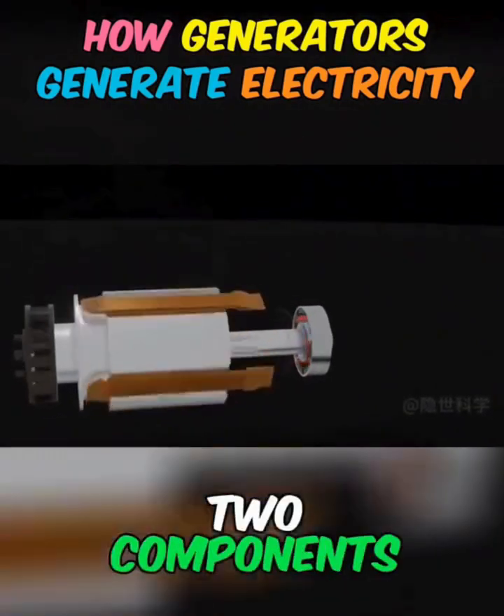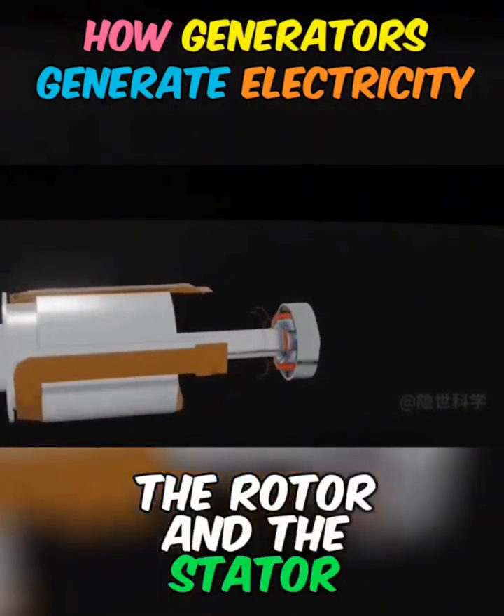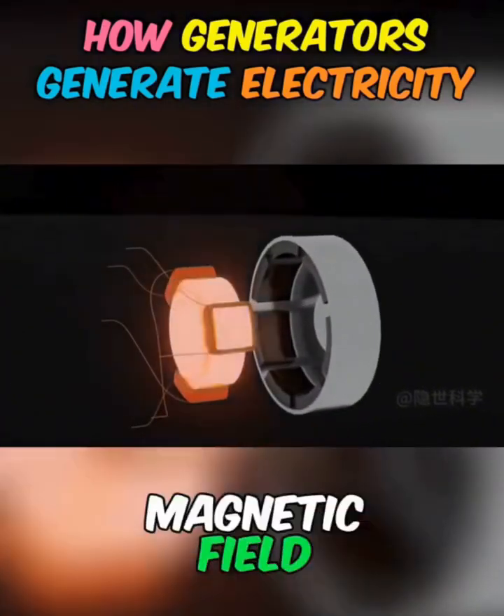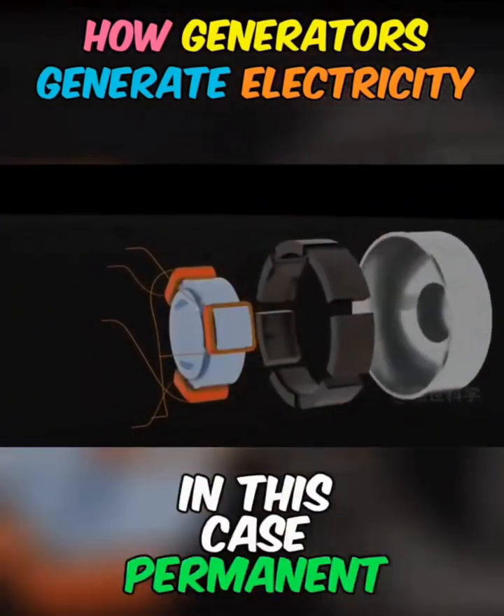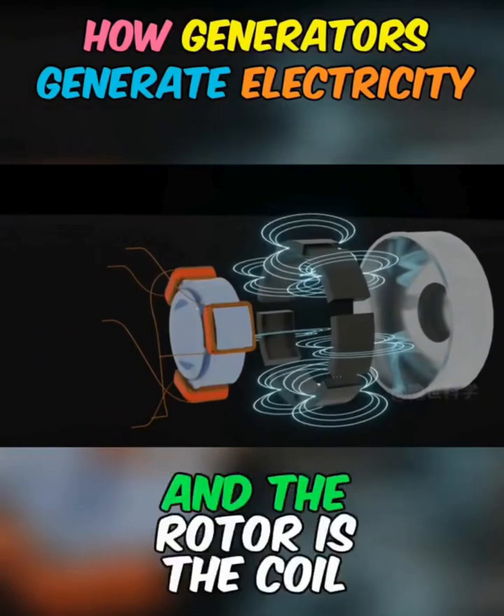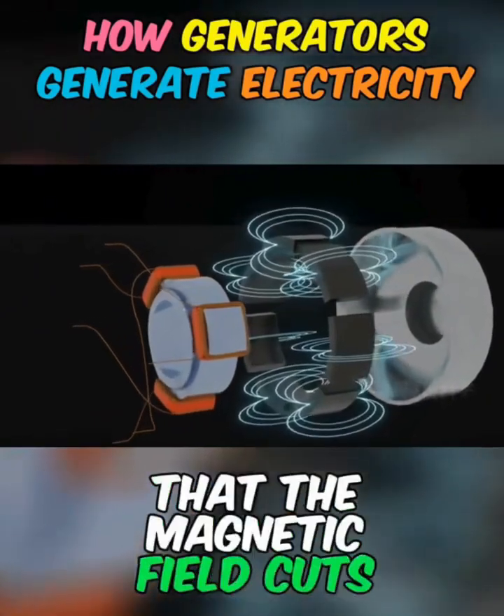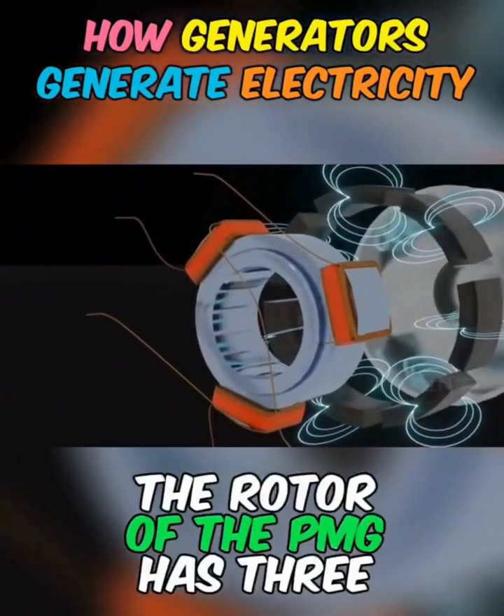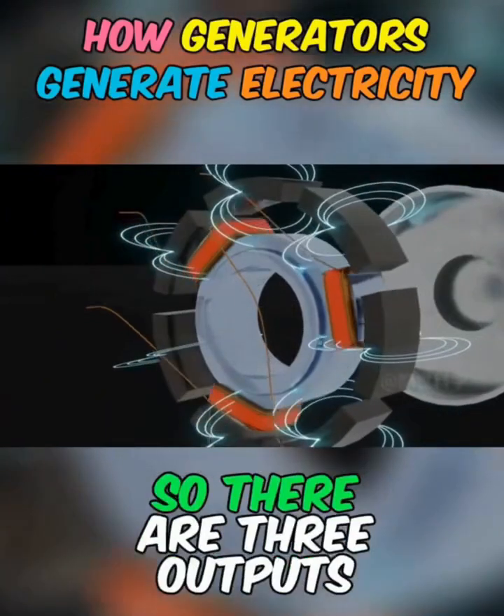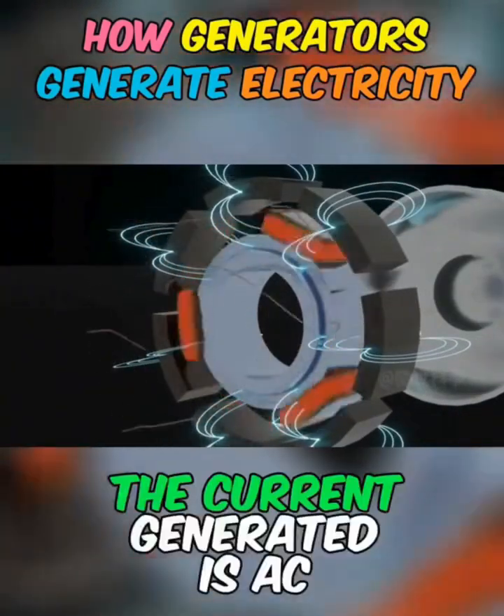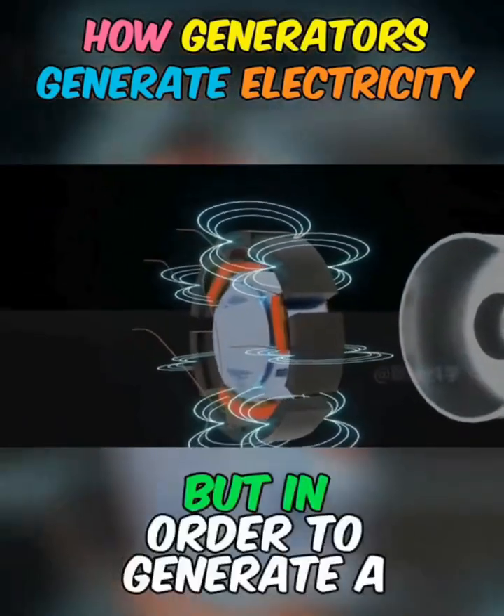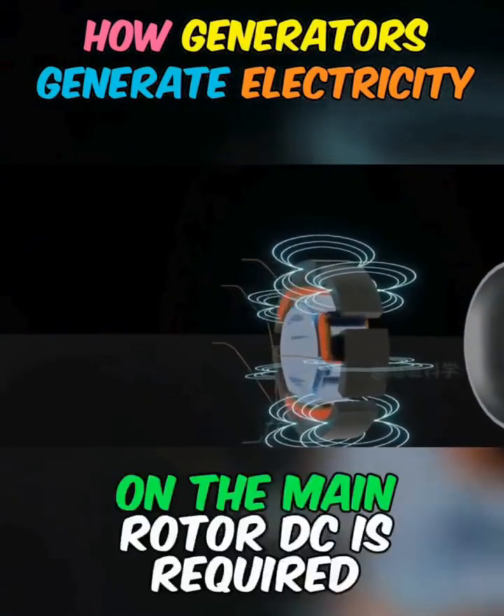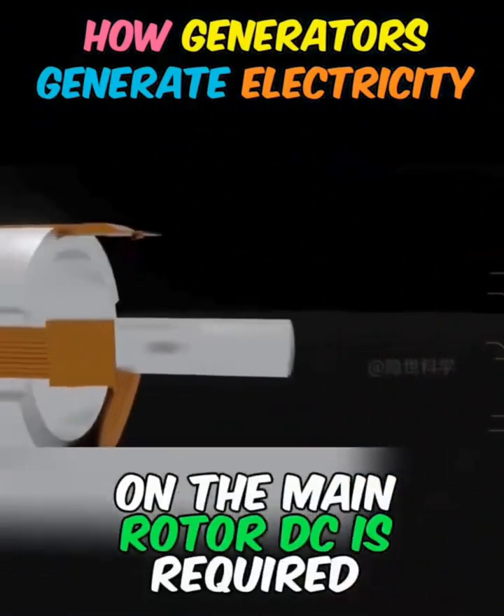There are two components, the rotor and the stator. The stator provides the magnetic field. In this case, permanent magnets are used, and the rotor is the coil that the magnetic field cuts. The rotor of the PMG has three, so there are three outputs. The current generated is AC, but in order to generate a magnetic field on the main rotor, DC is required.